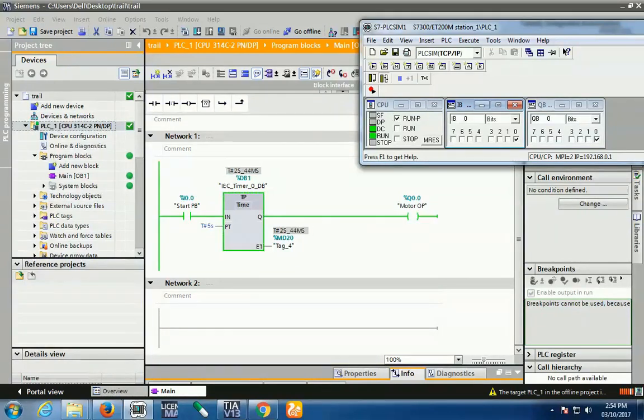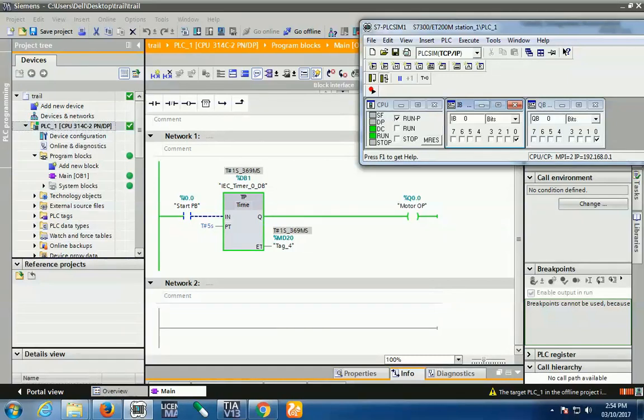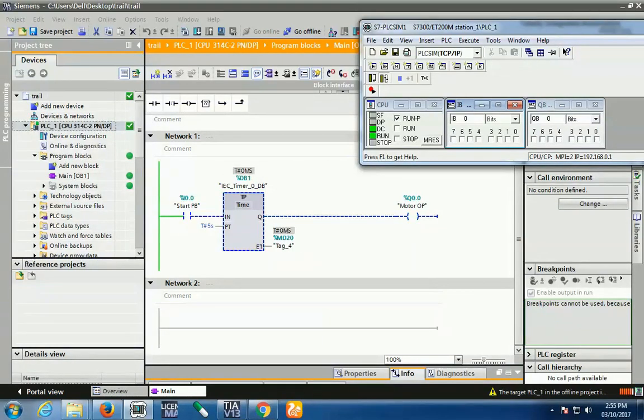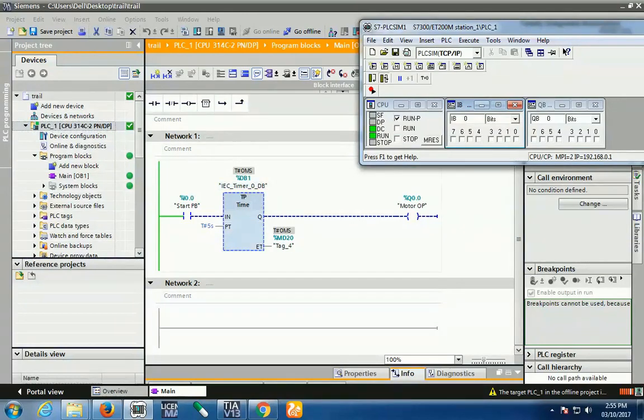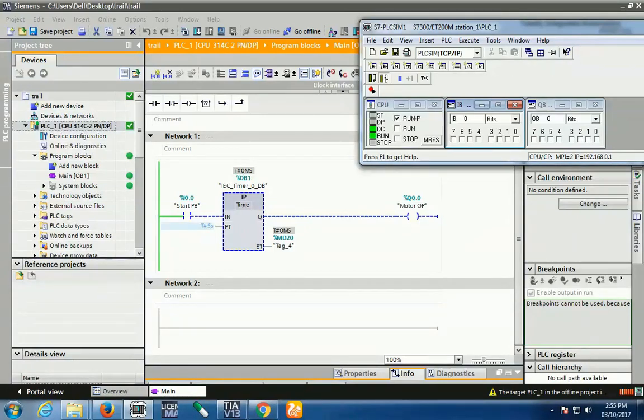In this case, if I release, my signal becomes 0, and when I press I0.0 again, my signal goes from 0 to 1, meaning a positive edge is detected in the enable command, and it starts again. Now if I press and in between press 2 or 3 times, it is not detected. Once your timer is activated, it bypasses your enable command before completion of the preset time.